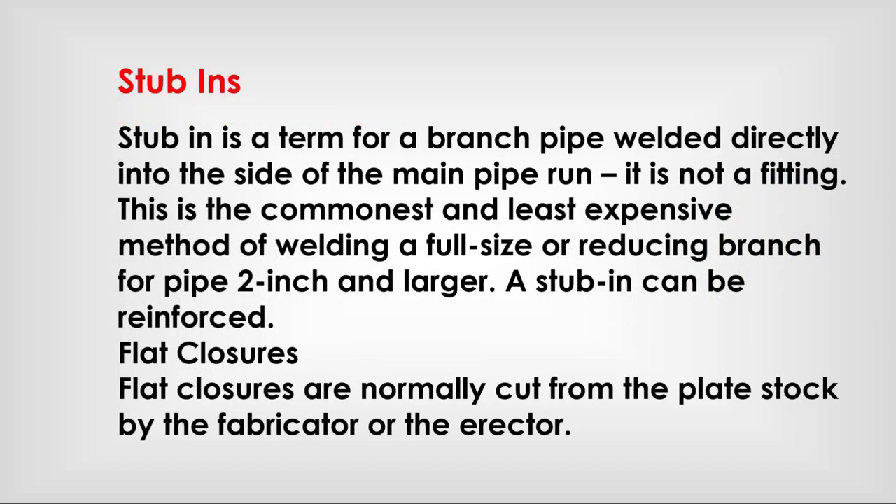Stub-in: a term for branch pipe welded directly into the side of the main pipe run. It is not a fitting. This is the commonest and least expensive method of making a full size or reducing branch. For sizes 2 inch and larger, the stub-in can be reinforced. Flat pads (reinforcing plates) are normally cut from plate stocked by the fabricator or erector.